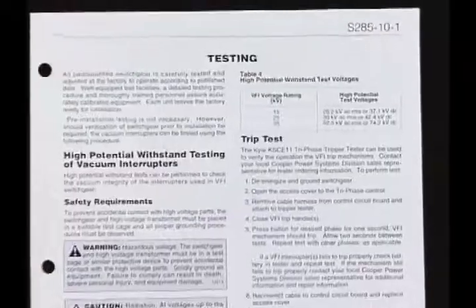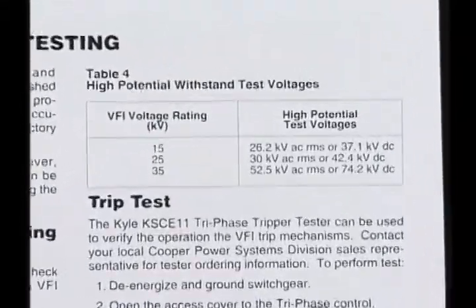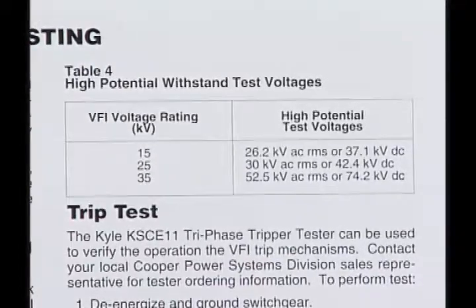High potential withstand tests are performed to verify the vacuum integrity of the interrupters used in VFI switchgear. For the recommended high potential withstand test voltages, refer to the VFI service manual. To prevent accidental contact with high voltage parts, the switchgear must be placed in a suitable test cage and all proper grounding and safety procedures must be followed. With the vacuum interrupters open, perform an AC high pot test for 1 minute or a DC high pot test for 15 minutes.